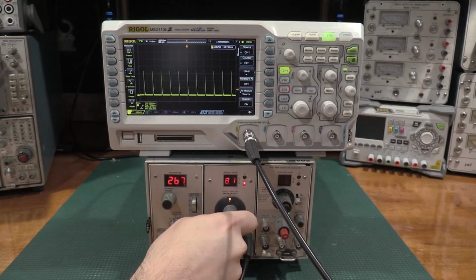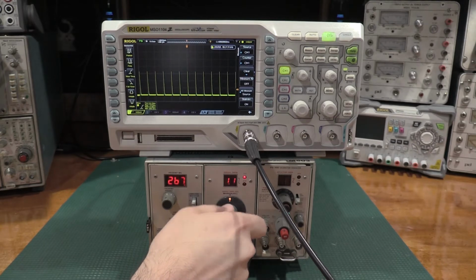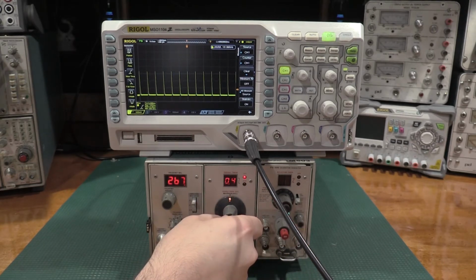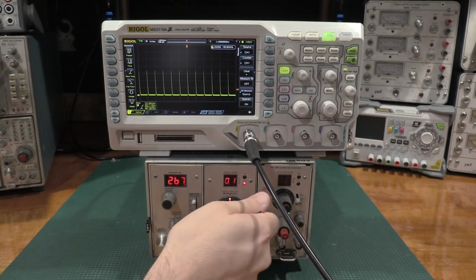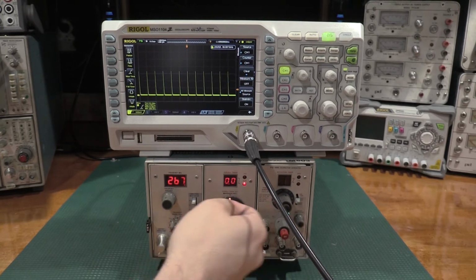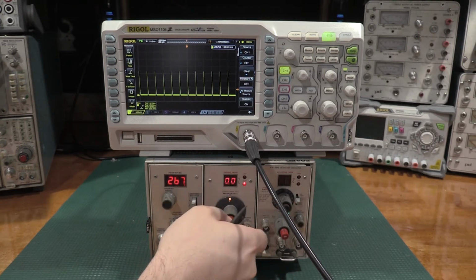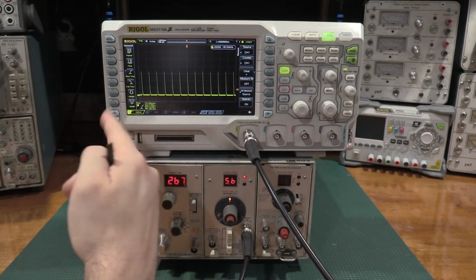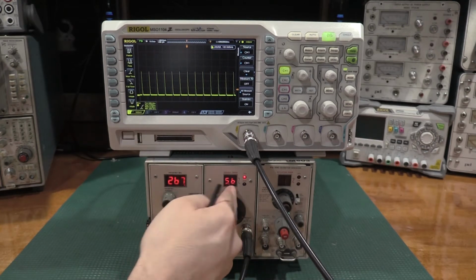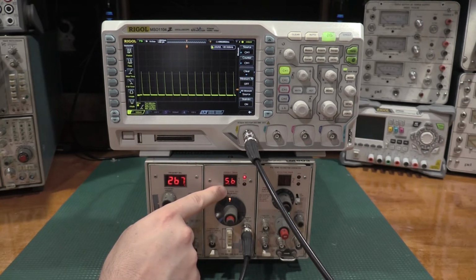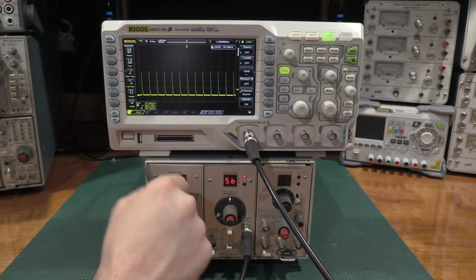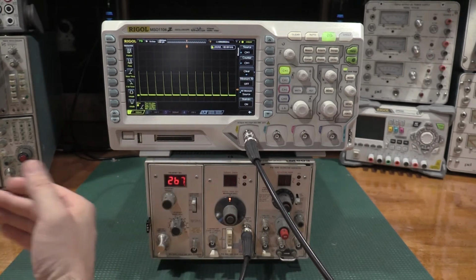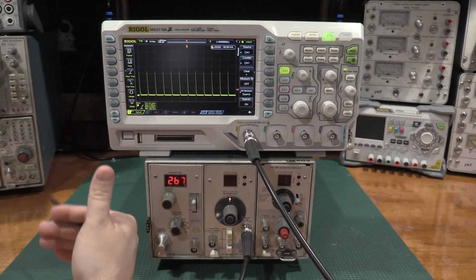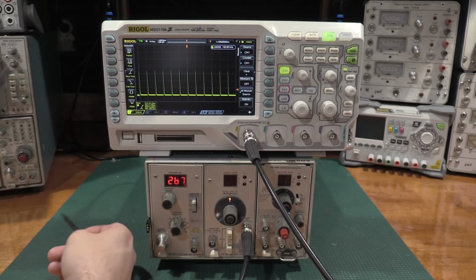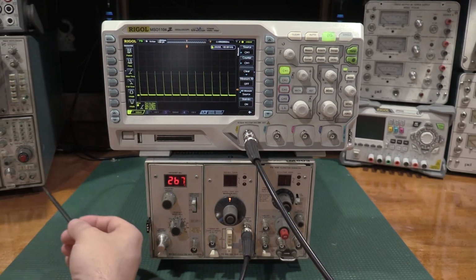So if you're checking a scope, like you get a new scope for the lab and you have no idea if the time base even needs to be adjusted, if it's far off or not, you can set up the different time bases, and then you can use the variable knob and the positioning control on the scope to line up the pulses, and that'll tell you the error. It'll calculate the error of the horizontal sweep. It was also a very precise way to measure pulses back before frequency counters, things like that.